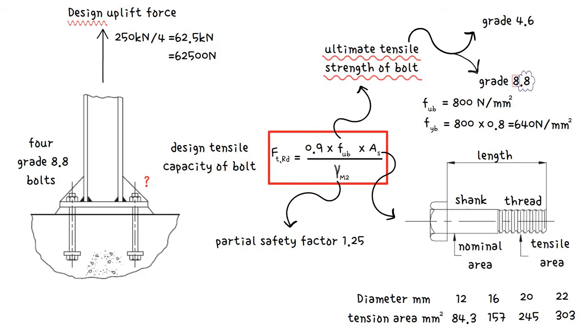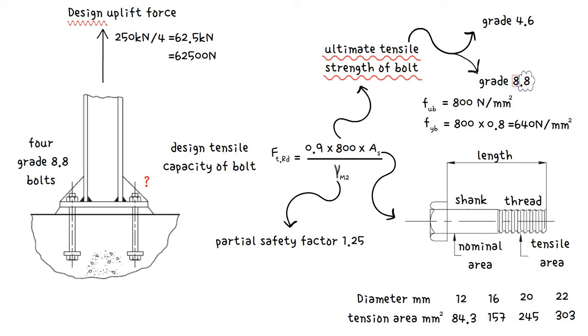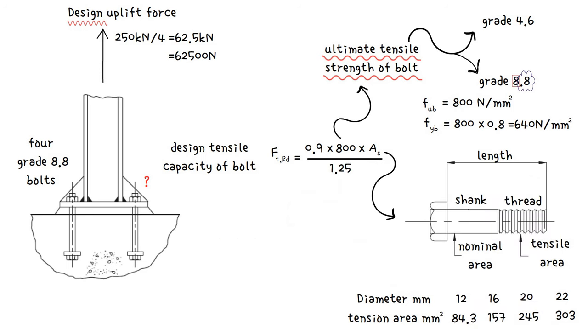As we mentioned, design tensile capacity of bolt equals 0.9 times ultimate tensile strength 800 N per millimeter squared, times the bolt tension area, which we need to figure out, divided by partial safety factor 1.25, equals design uplift for 62,500 N.